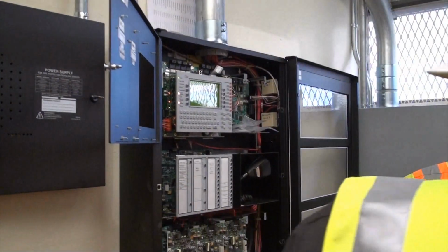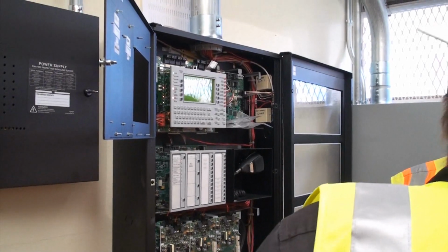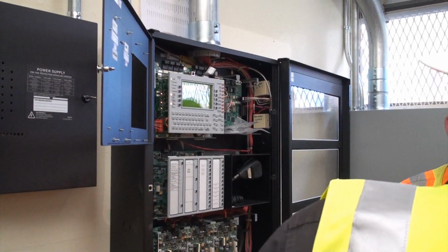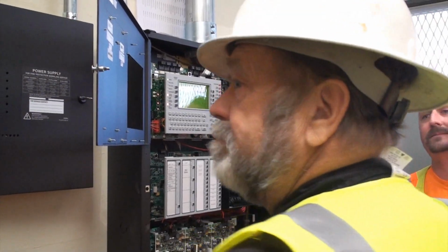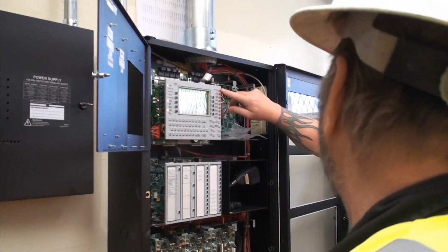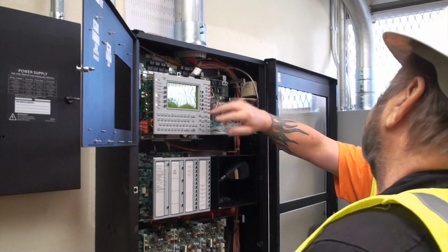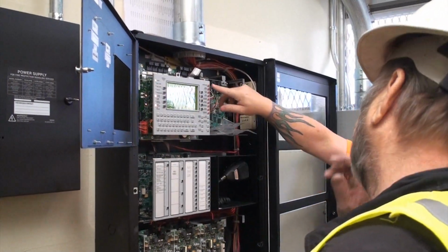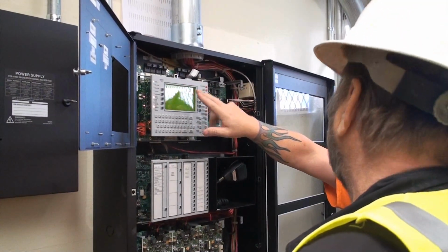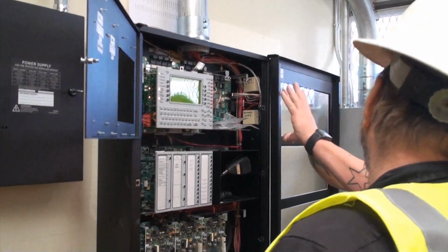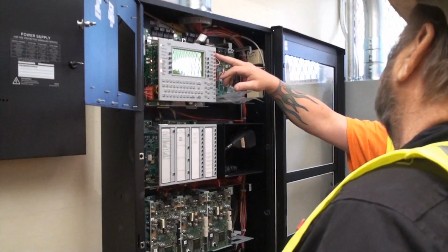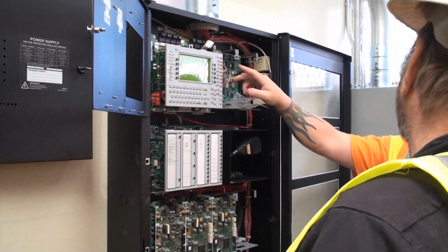Don't reset. Yeah, just acknowledge, silence, and then put the ticket in and we'll see what happens for the reset. You hit those buttons simultaneously, or? No, you'll hit it when it comes up. You'll see the red light come in, the fire alarm. You'll acknowledge it. It'll give you the readout of what it is. Oh, you hit acknowledge first? Yeah, correct. And that'll stop the beeping here. Okay. And then if you realize that it's a false alarm, you can hit signal silence.